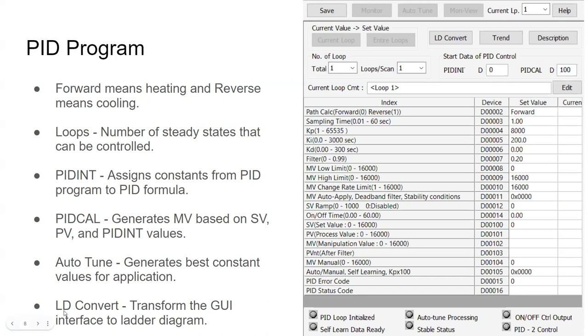The last point I want to cover is LD Convert — ladder diagram convert. You're transforming this GUI dialog box into a ladder diagram. Most people are comfortable with the GUI object, or you could be more comfortable with the ladder diagram — it's up to you. Note that when you press ladder diagram convert, there's no going back to the GUI object; you'll have to delete the program and recreate it from scratch. An advantage of ladder diagram convert is you get better control of the data registers and can control when the PID calculation starts and stops.